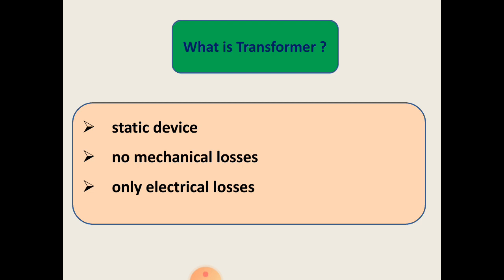In an actual transformer, output power is lesser than the input power. The efficiency of the transformer is defined as the ratio of output power to the input power. Usually there are a number of energy losses in actual transformers, due to which efficiency is always lesser than 100%. Most transformers have full load efficiency between 95% to 98.5%.